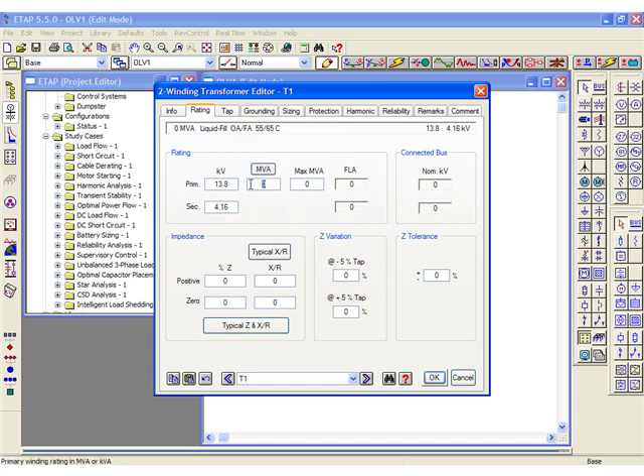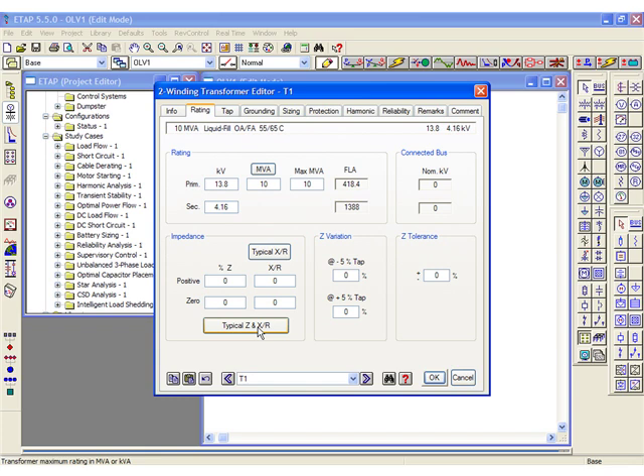When you click on the max MVA box, ETAP will automatically take that as 10. ETAP also provides typical built-in values for various parameters. For example, click on the typical Z and X/R to populate typical percentage impedance and X/R for the transformer. Select OK.